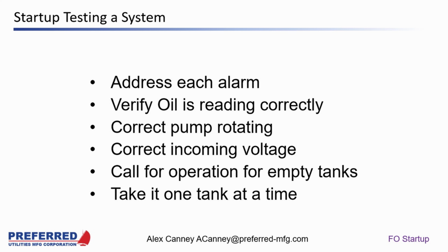So, Don, as you're working through the startup and getting towards the end, you're working through all the different alarms that are present. And I know for myself, it's rare that you start up a system that doesn't have several alarms on it. Once you've knocked out a lot of the alarms, what sort of things are you looking for as you wrap up, the end of the startup, maybe moving into commissioning mode? Verifying that I'm getting a call for operation for empty tanks, if it happens to be a brand new system and they're waiting for fuel. So I should only see those indicators or alarms saying I have a low level tank and it's calling for fuel and the pump's faulted. That verifies that that part of the logic in the control system is working.